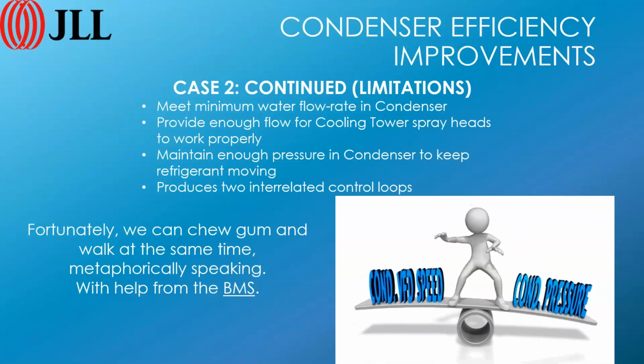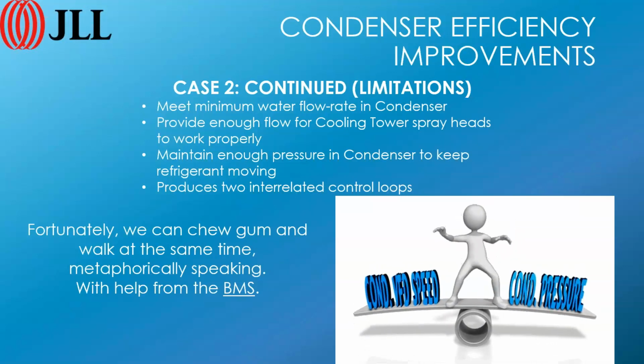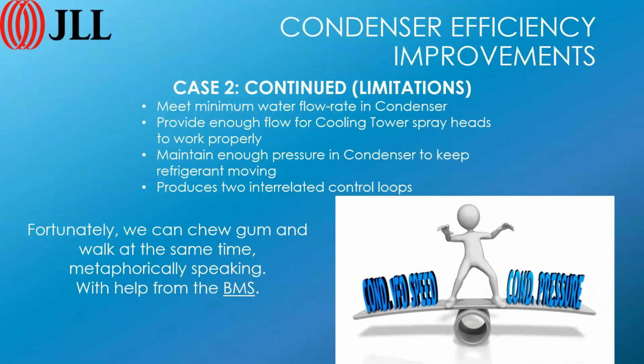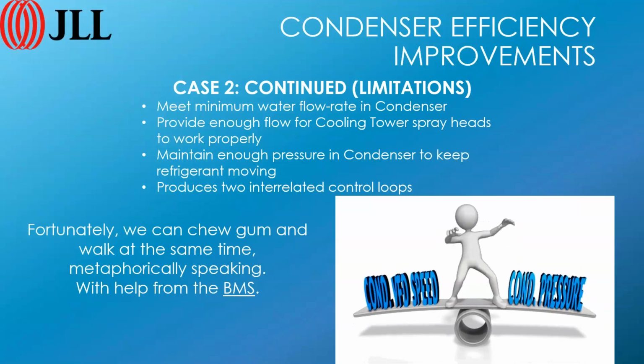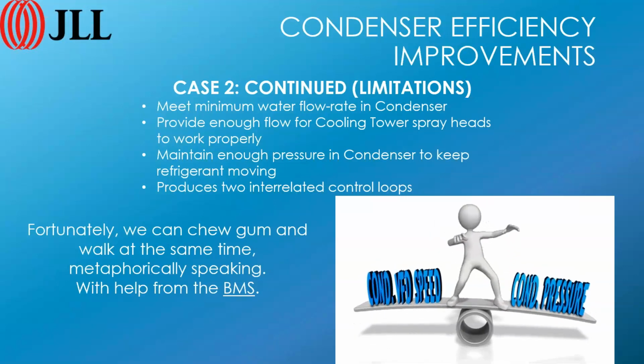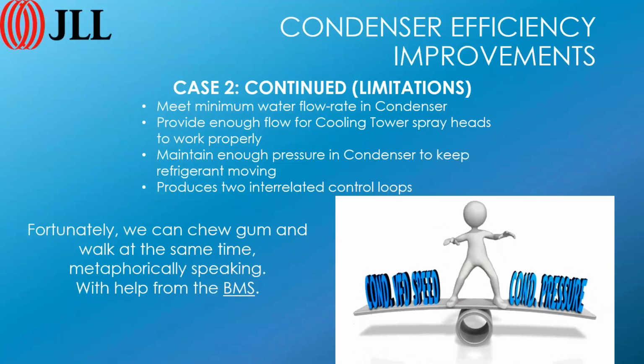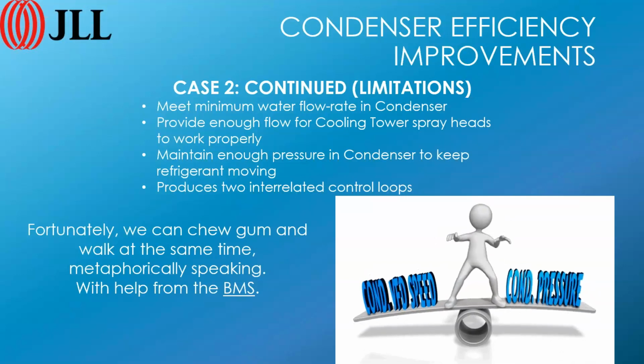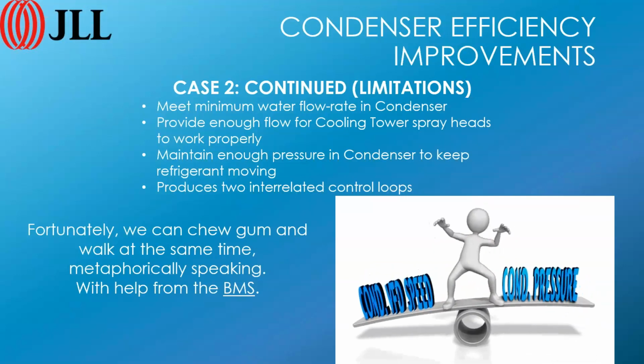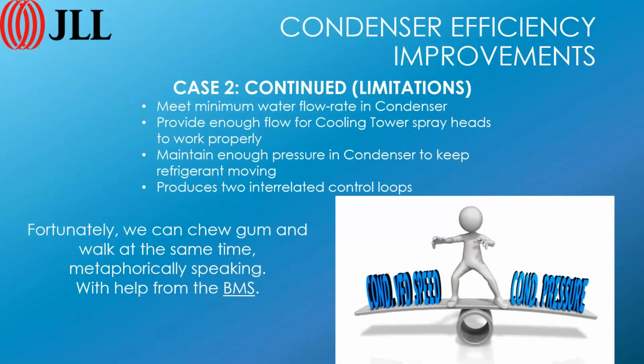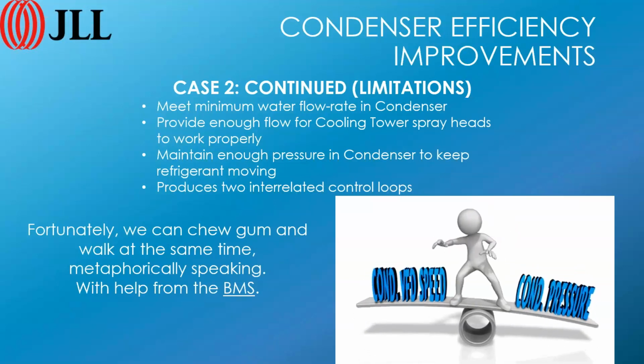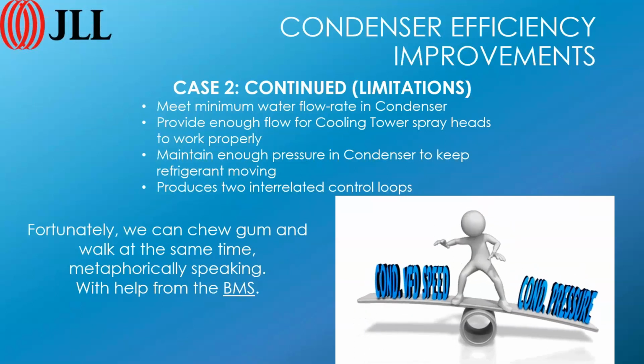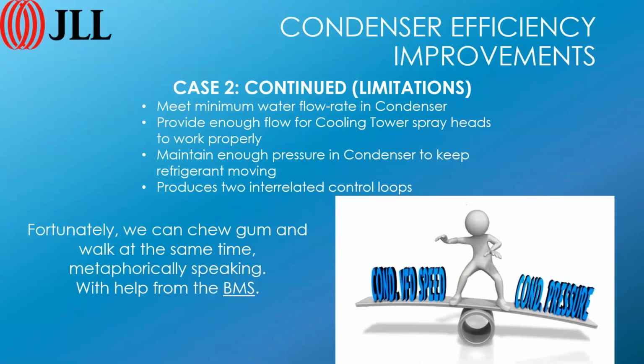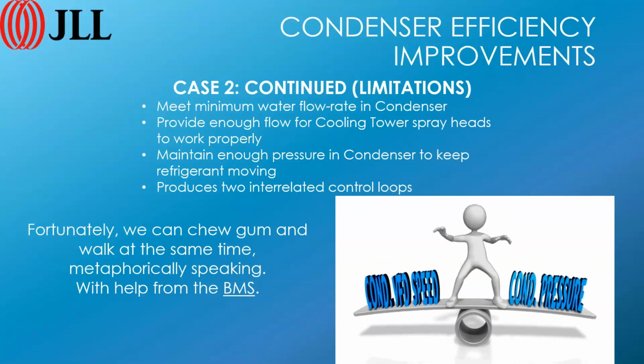And the way that you pick that number is you do a tube count on the condenser bundle and look at the water flow rates and figure out, based on the sediment that's in the area, what's an acceptable flow rate through all of those tubes. And that'll tell you your minimum flow rate. That's probably going to tell you also how cold you can make the cooling tower water. You'll find generally that in most cases 60 degrees is a reasonable minimum for tower water, and somewhere around 50% of condenser water flow is a reasonable minimum. That can vary depending on your local site conditions, but those are reasonable numbers to shoot for.